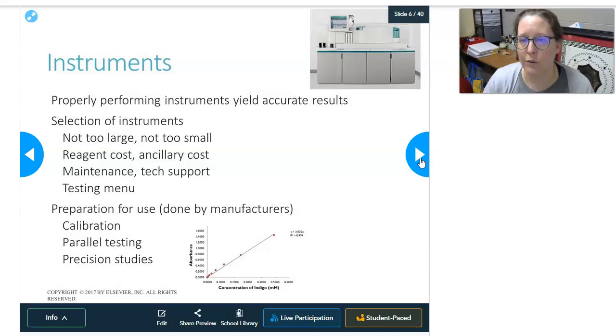You also will need to do parallel testing. So it's often a scenario where the old analyzer is still there, the new analyzer is in a location not too far from that old analyzer, and you want to take samples, run test panels on the old analyzer, and then run them again on the new one, and do this for a bunch of patients and compare. Is the new one running on par with the old one? Are you going to have to shift some ranges? Are you going to have to alert your physicians that we have new ranges because we switched analyzer methods? How is it affecting your patient results? Because if you don't communicate and tell them, and one of your tests is running higher on the new analyzer, they may think, oh, there's something wrong with my patient, when in fact all that happened is you switched analyzers.